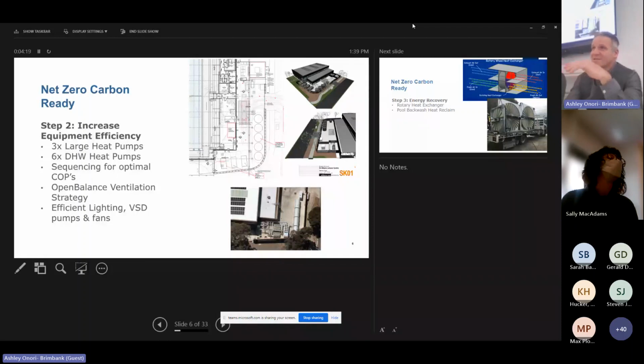What it does do, that I know, is reduce the fan energy requirements by about 30%. It creates still air films over all surfaces, meaning we've got hardly any condensation, or none at all. We can reduce the evaporation from the pool itself significantly. One of the best features, I believe, is that it reduces stratification to almost nothing, meaning the temperature at the ground is almost the same as right under the surface.